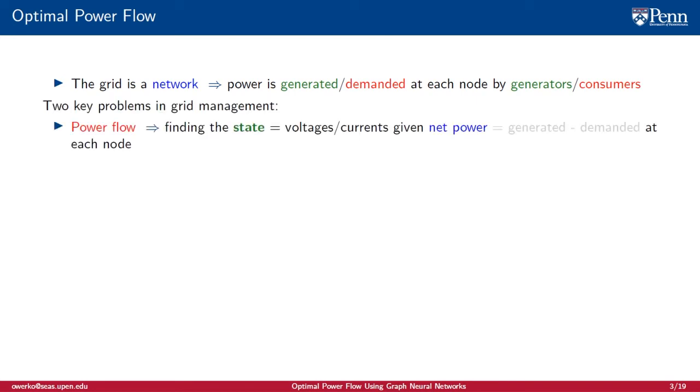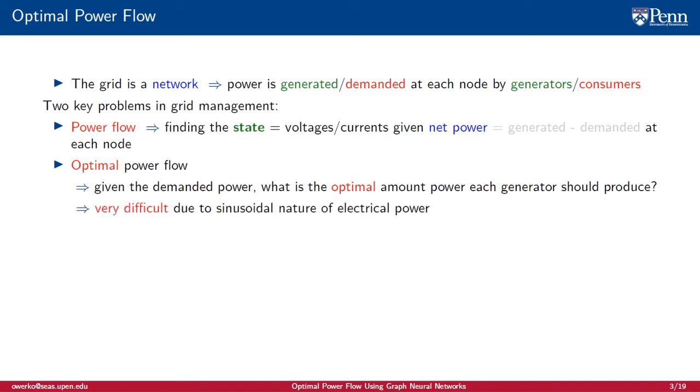There are two key problems in grid management. Power flow is finding a network state, given the power generated and demanded at each node. This is relatively simple to do. Optimal power flow is much harder. Given the demand at each node, we want to answer the question, how much power should each generator produce? It's very difficult due to the sinusoidal nature of electrical power. And unfortunately, approximations fall short in one way or another.